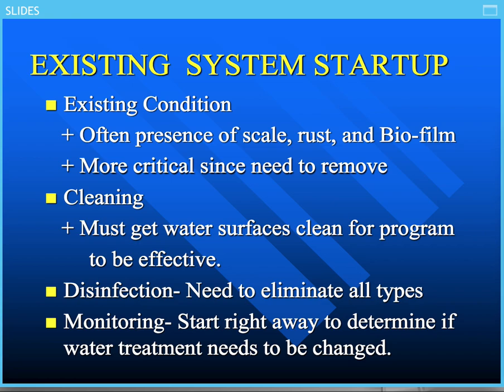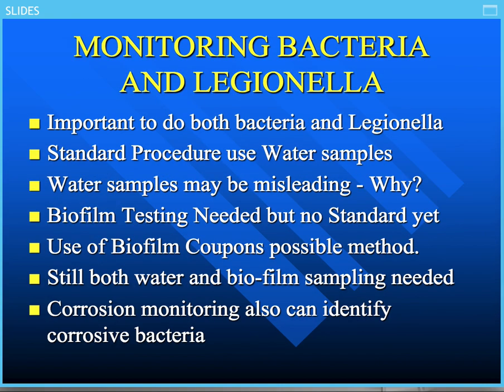Now, biological control: you can use dip slides, etc. You could use any type of the new technology to come up with water quality measurements and how much bacteria is there. So you've got to make sure that if you're identifying any corrosive bacteria, you have a good biological program to take care of it. Anyway, could I have the next slide, please?